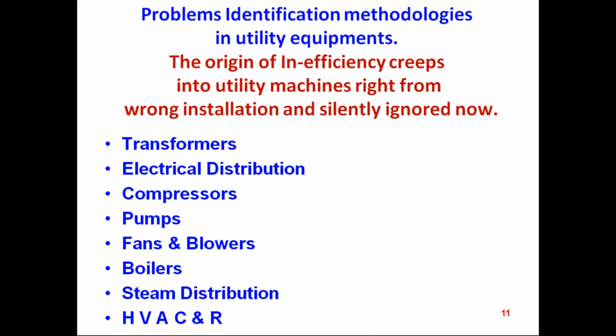It is the same with boilers, especially package boilers, where the losses are more. As an energy auditor we always suggest a moisture separator installed at the outlet of the boiler, which will definitely reduce the water content in the steam, or in other words make the steam drier. The dryness fraction of the steam has to be excellent. It should be almost 95% dry, and that will maintain the thermal productivity for the given system. This applies to the boiler and steam distribution. Then comes the HVAC. Next, please.